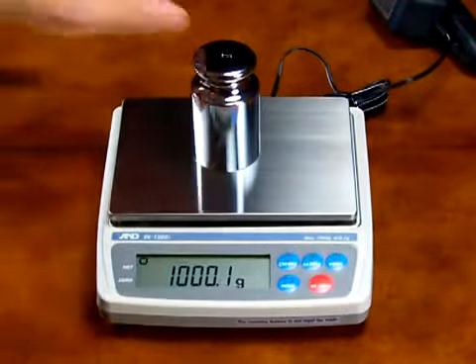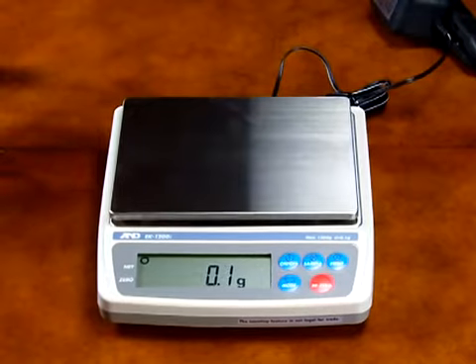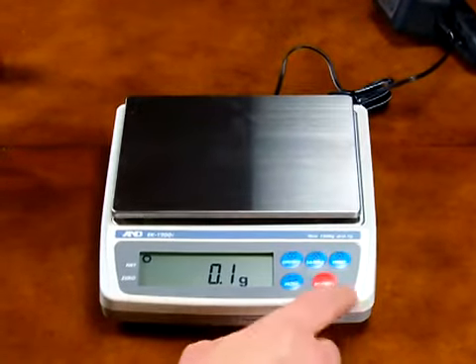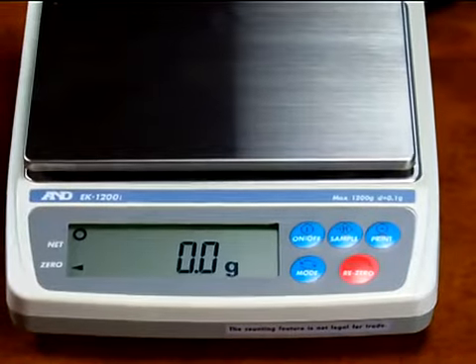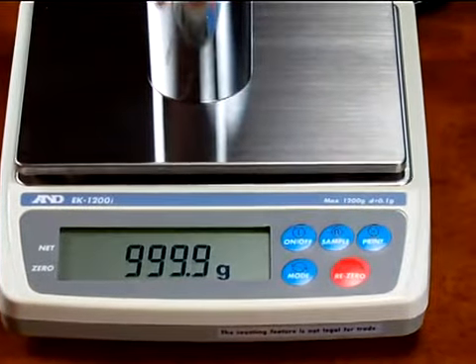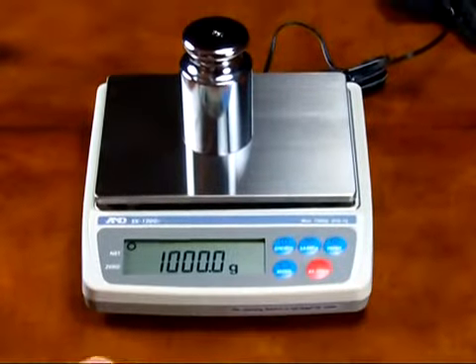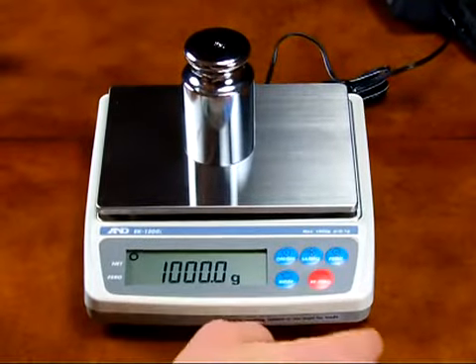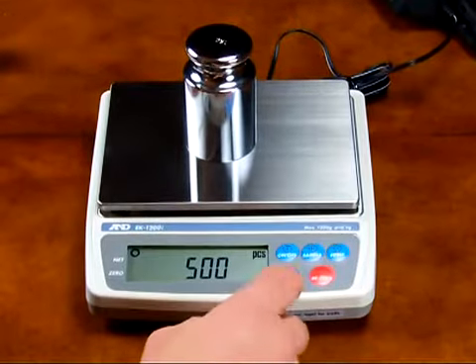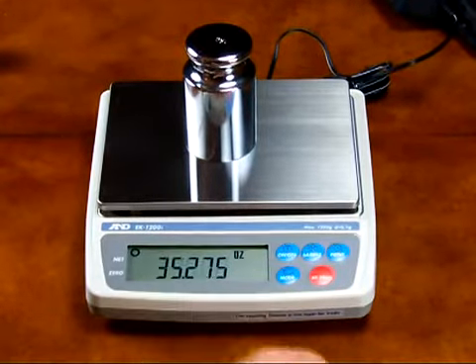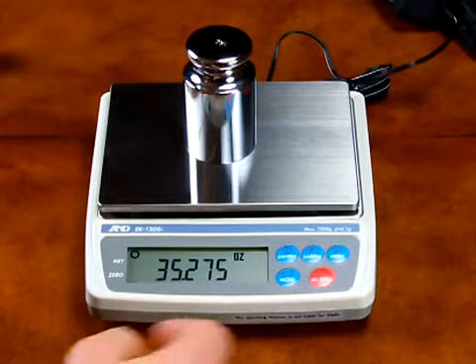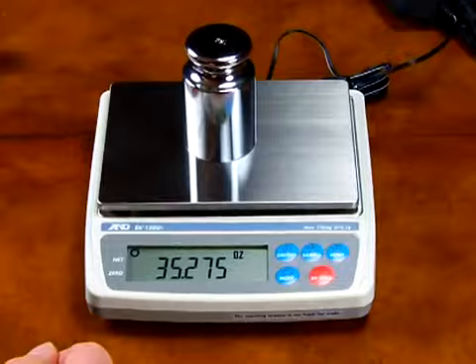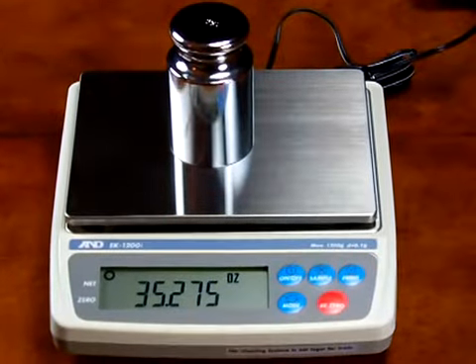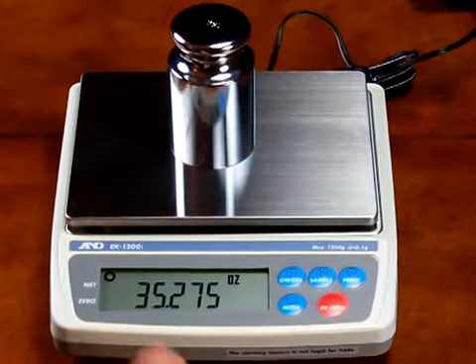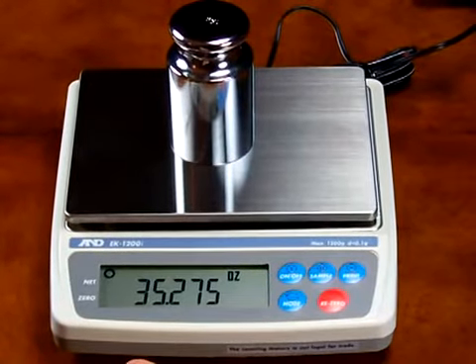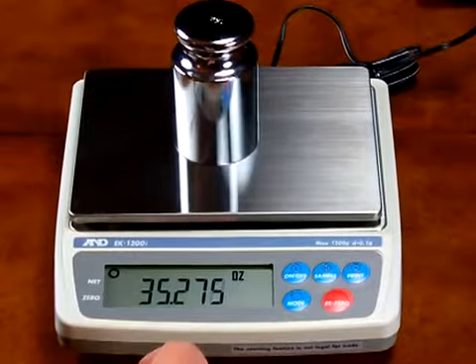So today we'd just like to show you the different weigh modes also. So we will tare this balance out, and we'll put 1 kilogram on, and again, that's within tolerance. Simply by pressing the weigh mode button, we're in grams. The balance goes into piece count mode, percent mode, and then here we have ounces. So if you were a chip manufacturer and you wanted to do spot checking of your 8-ounce bags of potato chips, this scale reads in ounces, legal for trade, to 0.005 ounces.